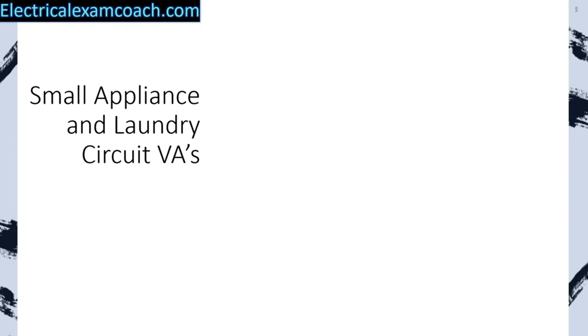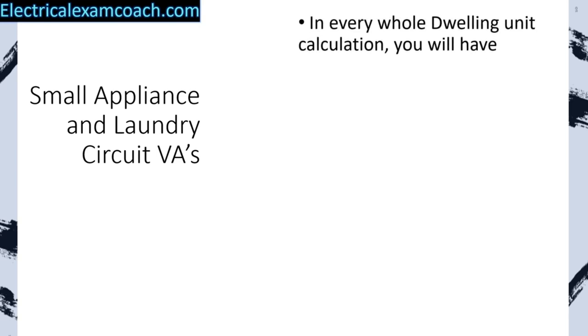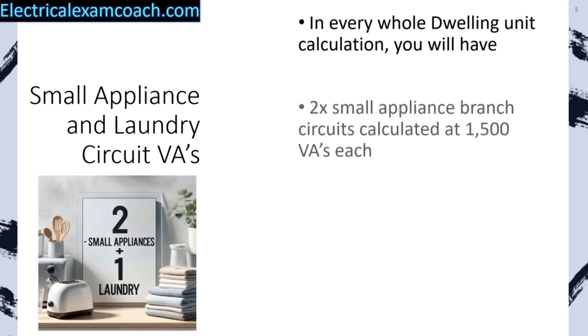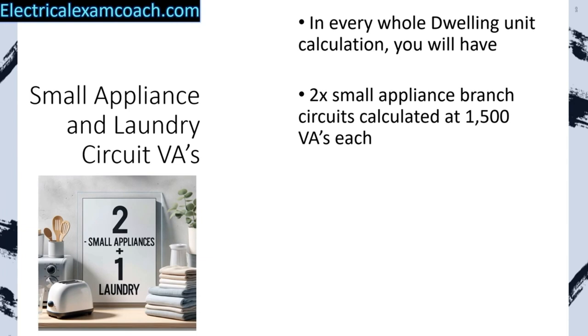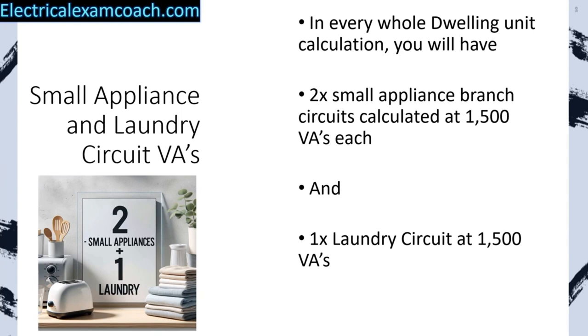Now that we've learned about our 3 VAs per square foot, we have to learn about what's called our small appliance and laundry circuit VAs. In every whole-dwelling-unit calculation, we're going to have 2 small appliance branch circuits calculated at 1,500 VAs each, and one laundry circuit calculated at 1,500 VAs each — for a total of 4,500 VAs. We only add this on to the general lighting load and receptacles before demand factors when doing a whole-house load calc. We are not going to add it on to something like an individual dryer or range — those are calculated individually.